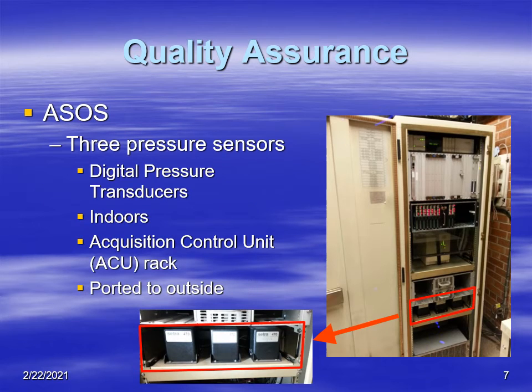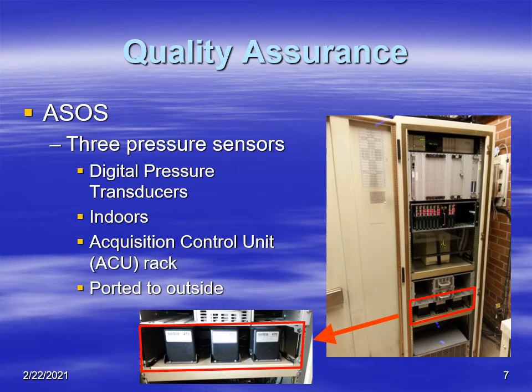The next topic we'll consider is quality assurance. Measurements of atmospheric pressure at the surface are made by automated surface observing systems, or what we call the ASOS. The ASOS has three pressure sensors, which provides backup and redundancy. They are digital pressure transducers — specifically, the Setra 470 pressure transducers. They're located indoors in the acquisition control unit rack, as shown in the picture highlighted in red, and you can see that they're located side by side. Each one of those is connected to the same static line, so they're all measuring the same static pressure.